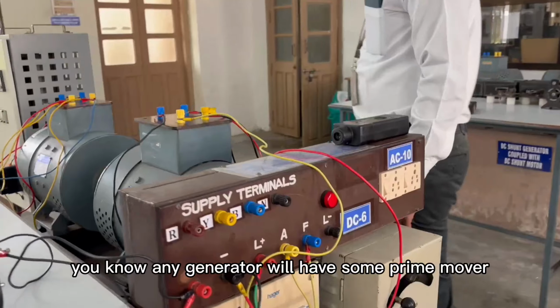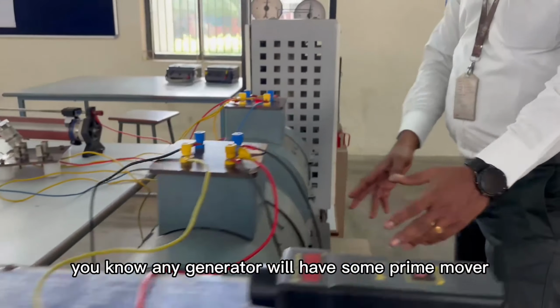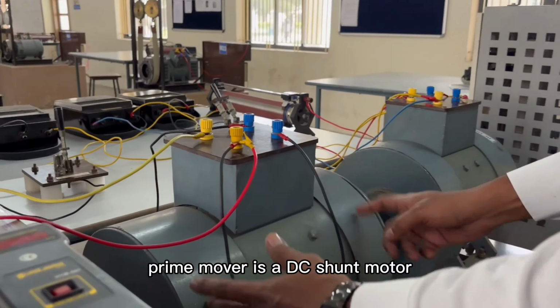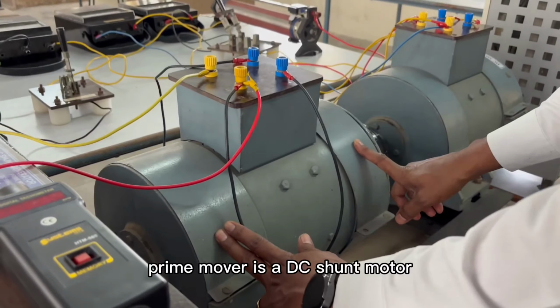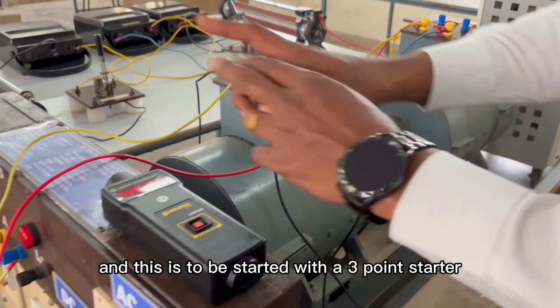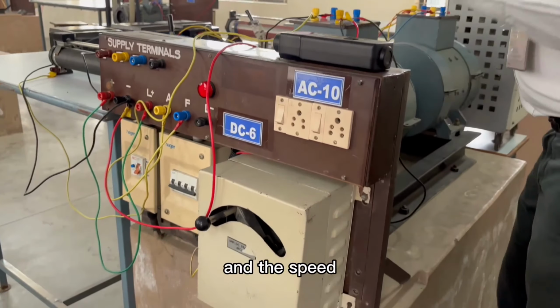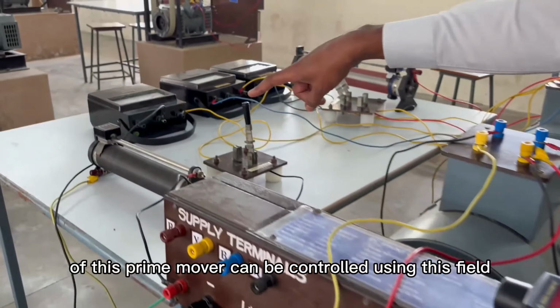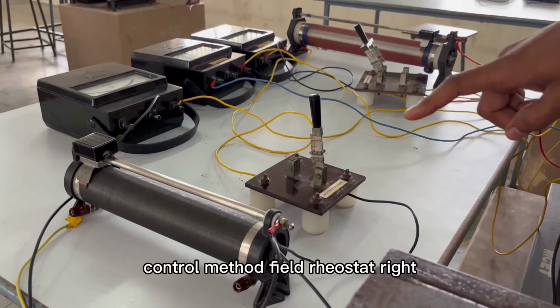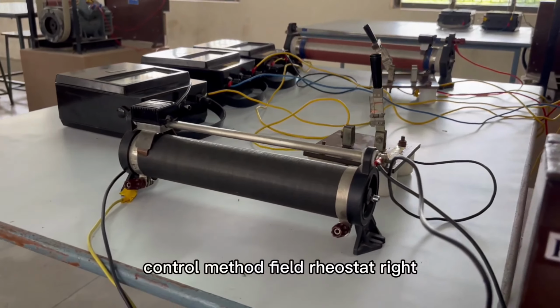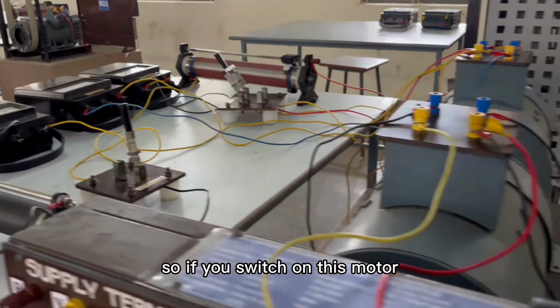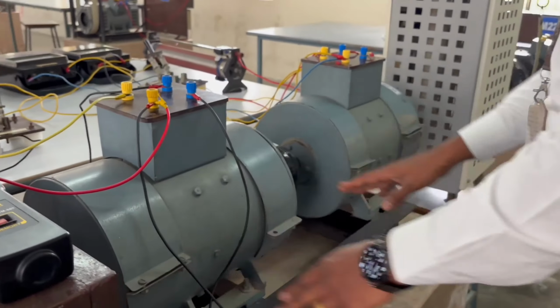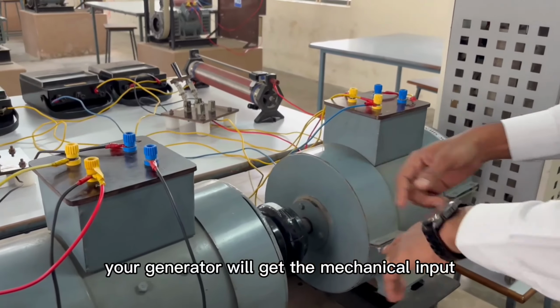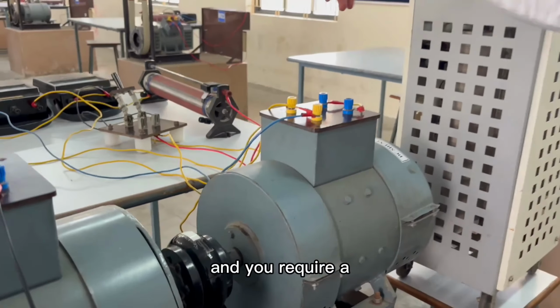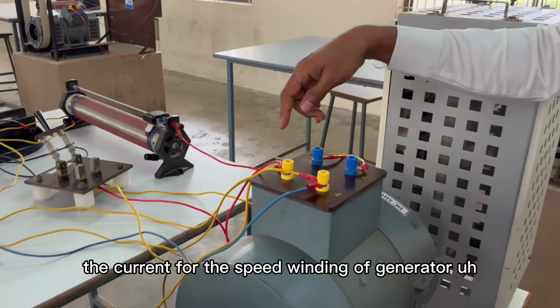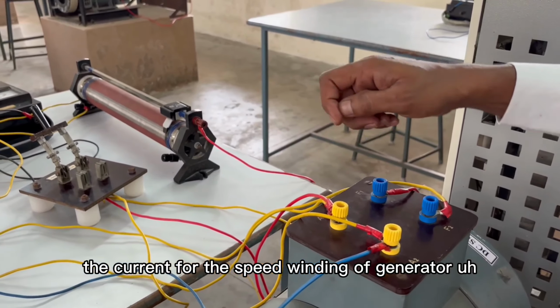Any generator will have some prime mover. This is the prime mover. The prime mover is a DC shunt motor, and this is to be started with a 3-point starter. And the speed of this prime mover can be controlled using the field control method, the field rheostat, right? So if you switch on this motor, this prime mover, your generator will get the mechanical input, and you require field current for the field winding of the generator.